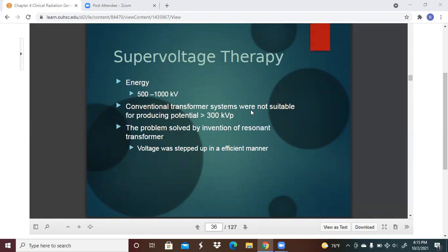So, supervoltage therapy. Now we're getting closer and closer to megavoltage therapy. Energies here are basically 0.5 to 1 MV, or 500 to 1000 kV. Conventional transformer systems were not suitable for producing potentials of greater than 300 kVp. And the problem was solved by the invention of the resonant transformer. Voltage basically was stepped up in an efficient manner.